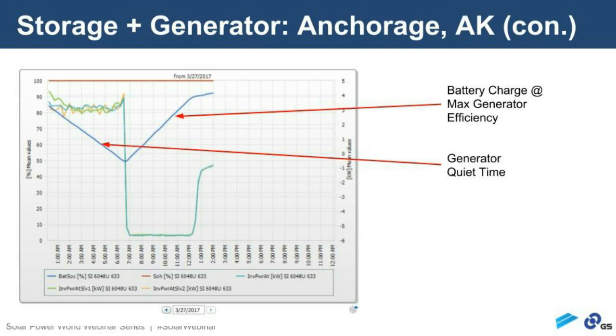So this was a simple use case, again, GS SLR 1000. So we are able to cycle it much deeper than a traditional lead-acid battery. Normally, we would only design for a daily cycle if we were using a flooded battery or a high-quality AGM. Probably we wouldn't go beyond 70% or 60% state of charge on a daily basis. But with this battery, we consistently go to 50 or below, all the way down to 30% state of charge or 70% discharge.